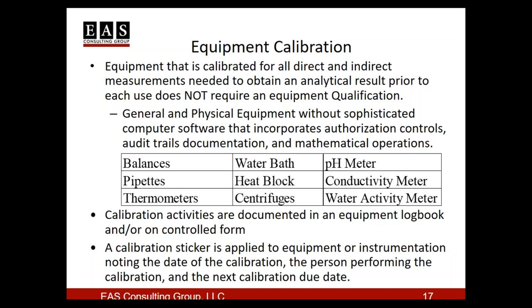This includes things like balances, pipettes, thermometers, water baths, centrifuges, pH meters, that sort of thing. Balances typically have a daily weight verification done on each piece and each balance, as well as a 6 month or 3 month type calibration done externally. Pipettes are usually calibrated every 3 or 6 months, but it's a direct measurement being made. So as long as that direct measurement is holding and within calibration, there's no need to qualify that piece of equipment. This is equipment generally considered to be mobile.